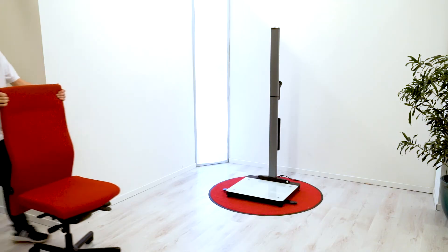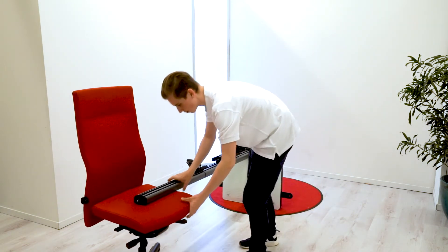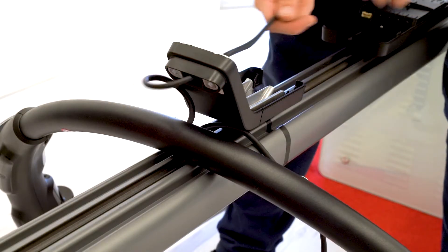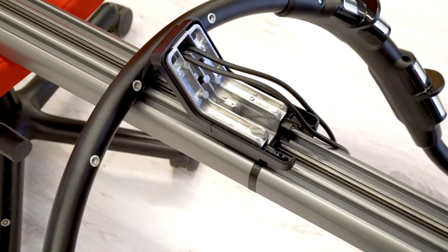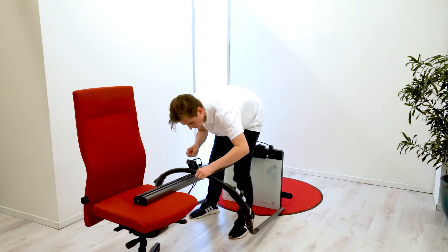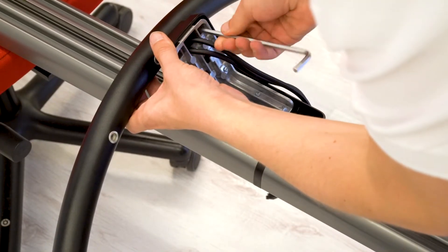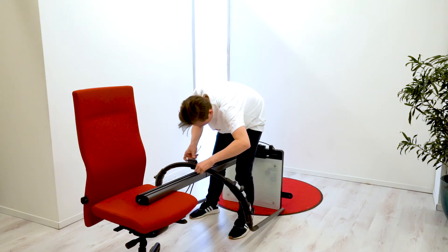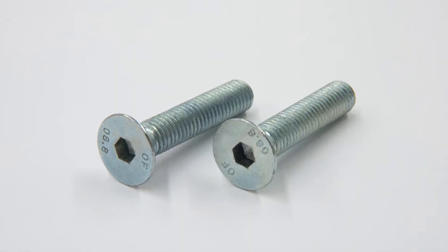Place a box or a chair in front of the device and tilt the device forward until the column rests on the elevated surface. Guide the two BIA hand electrode cables from the center of the standing aid through the opening at the top of the handrail connector. Lift the standing aid over the column such that the two poles align with the holes in the crossbeam. Attach the BIA standing aid to the handrail connector using the two M6x12 screws and the 5 mm Allen key. Then use the M8x40 screws to attach the poles to the crossbeam.